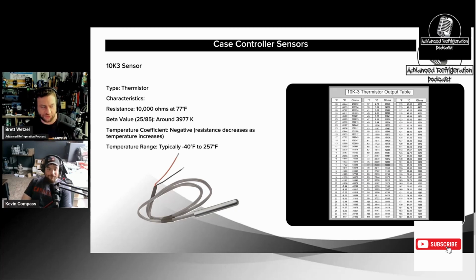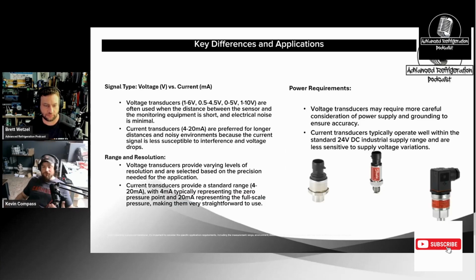So you want to talk about pressure transducers now? Okay, let's go to pressure transducers. Now, pressure transducers, guys, they come in all shapes, flavors, and sizes. If you're talking Copeland stuff, it's going to be 0.5 to 4.5 for their general can stuff. It could be 0 to 100, 0 to 200, 0 to 500, 0 to 650, 0 to 1,000, 0 to 2,000. All the ranges are on there.